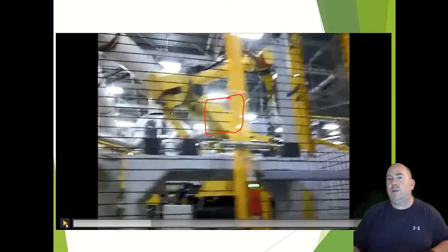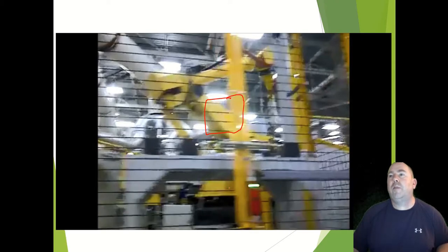This device here. See another device here. These red devices on these doors, that is a locking door switch. So you need to request to open this door. When we say request to open, this is solenoid locking.